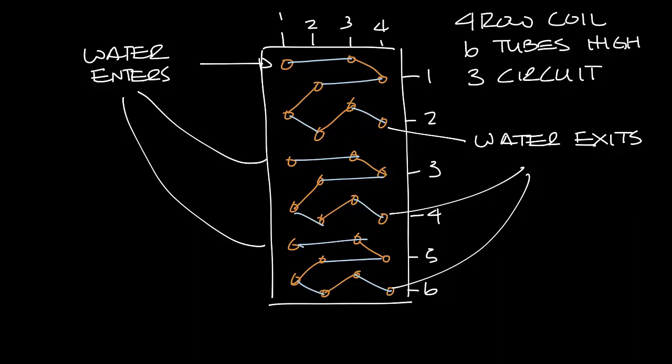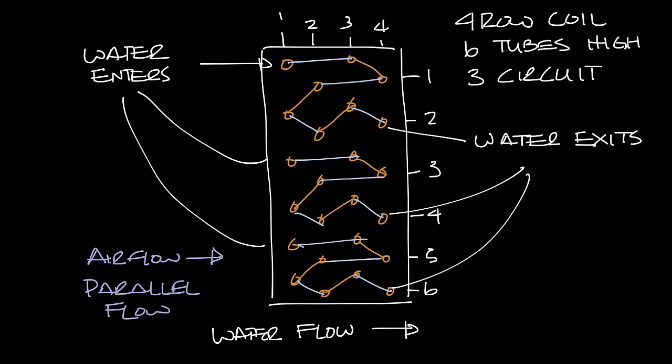So the way I drew this water coil, the water will flow from left to right. If you remember back to the counter flow and parallel flow podcast, if the air flow is moving in the same direction left to right, this is a parallel flow water coil, and if the air is moving in the opposite direction from right to left in the drawing, then this is a counter flow water coil.